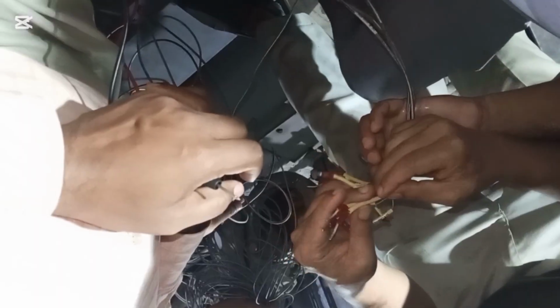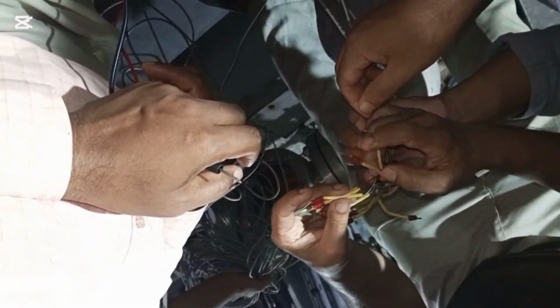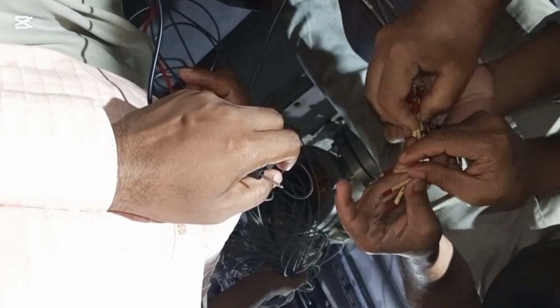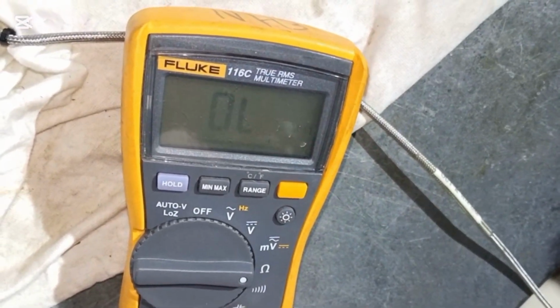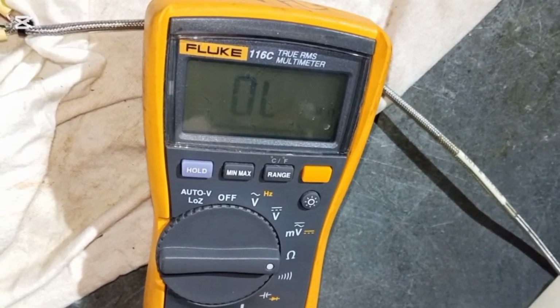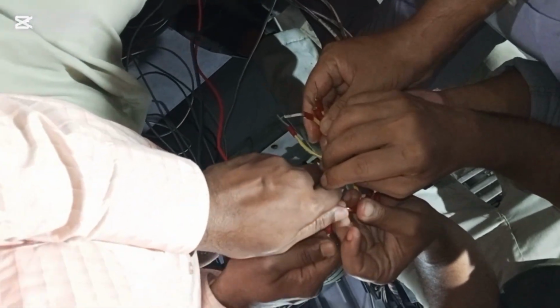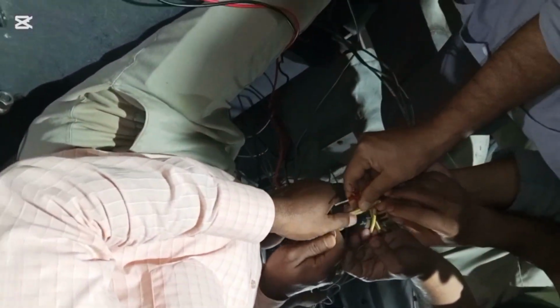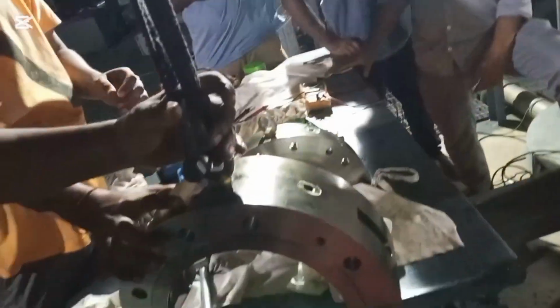Here the sensor resistance value is likely 2.2 ohms, and here is the different sensor cable. Here is one common cable and another 4 are sensor cables. So at first we identified the cable which is common, and then measured with the multimeter the ohmic value. Here the resistance value, one and 4 ohms, is showing. Also at the time of dismantling the sensor, we measured the value.